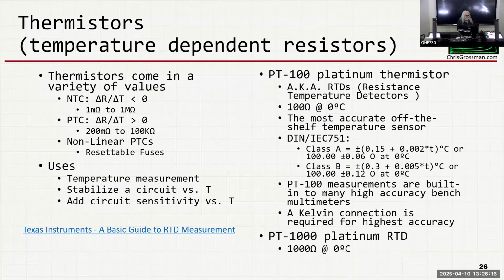Now there's a specific kind of thermistor called a PT100, platinum thermistor. Sometimes you'll see it called a platinum RTD, RTD just stands for resistive temperature detector. People get confused, but it's just a thermistor, a specific resistor made out of platinum, made to be exactly 100 ohms at 0 degrees C. It's the most accurate off-the-shelf way to measure temperature you can get. You can get within plus or minus 0.2 degrees pretty easily, whereas a thermocouple is within a couple degrees.